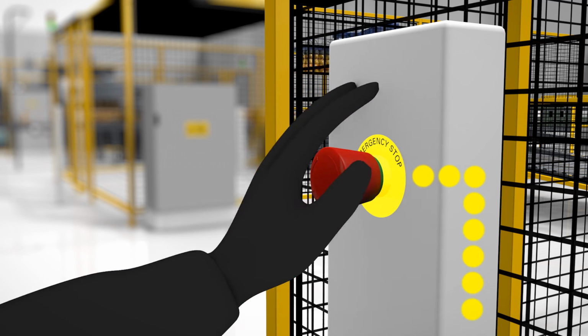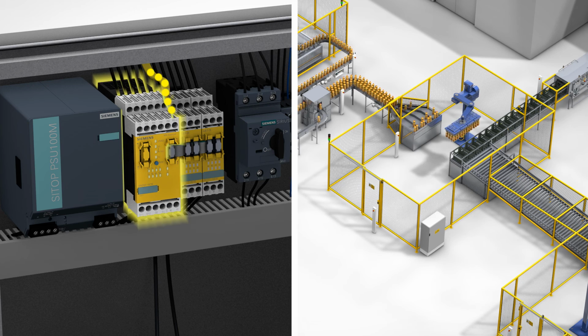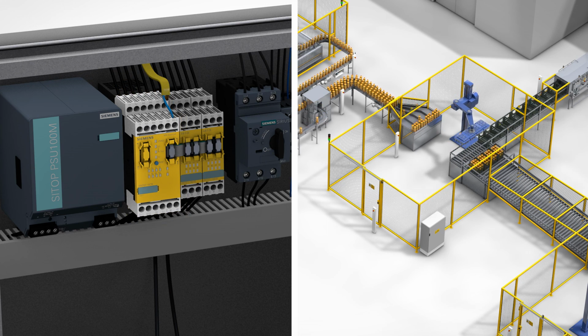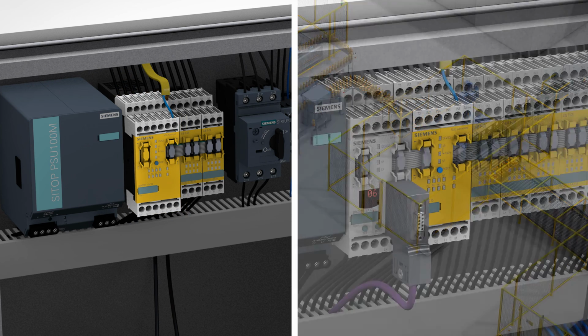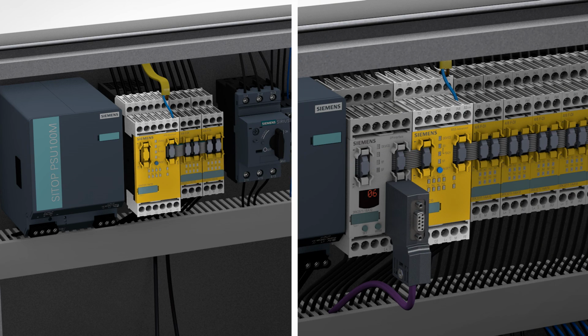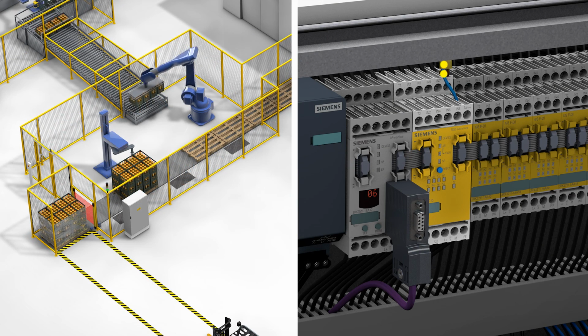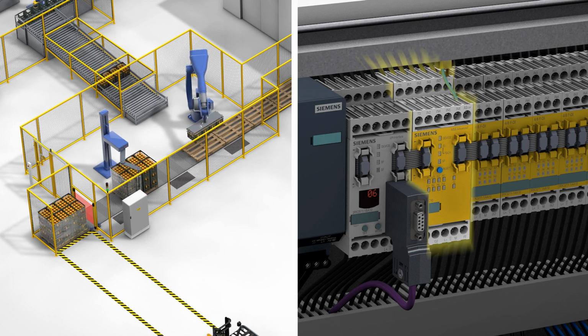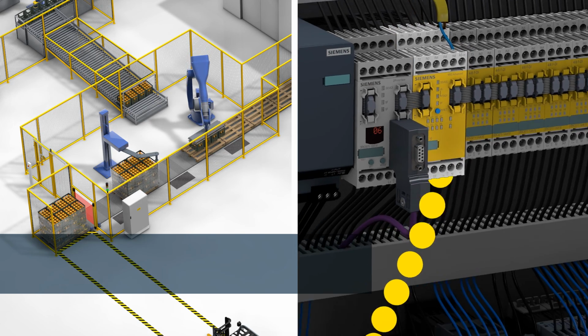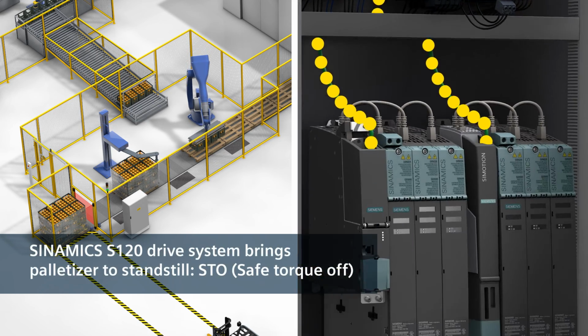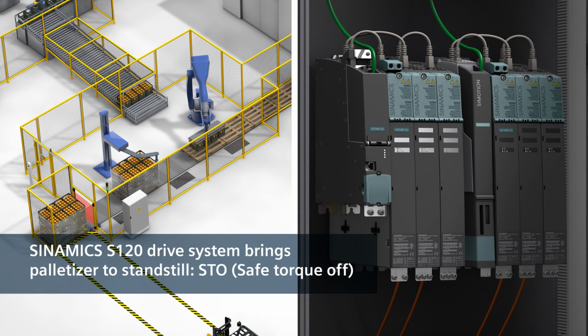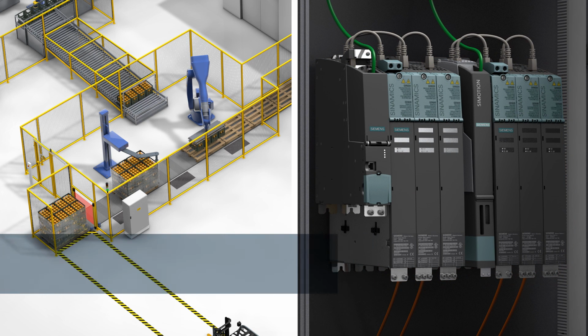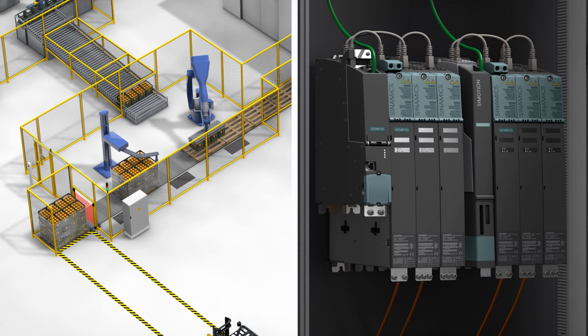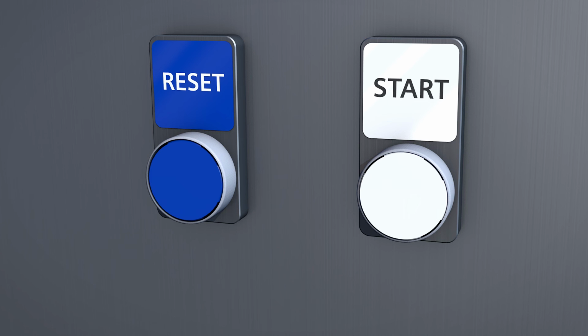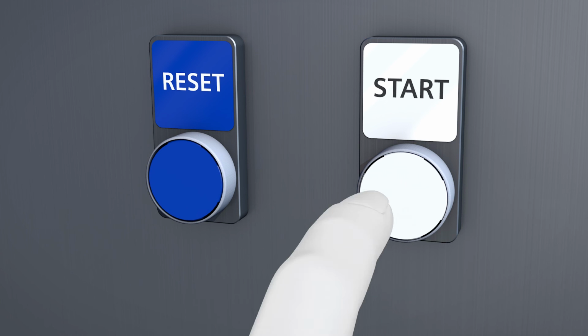If the emergency stop is triggered on the packaging unit, the MSS evaluates the signal and safely shuts the packaging unit down. At the same time, the MSS on the palletizer receives a shutdown signal via ASI-Safe. The MSS brings the drive system of the palletizer to a safe standstill and protects against undesired restart. When the cause of the emergency stop has been eliminated, both plant sections can be released again and restarted.